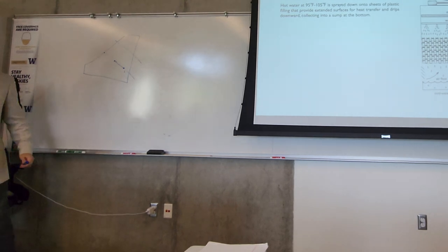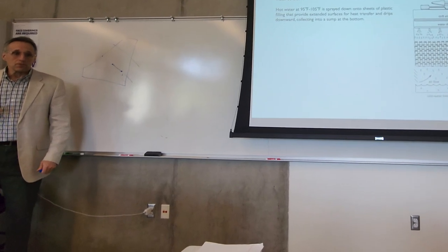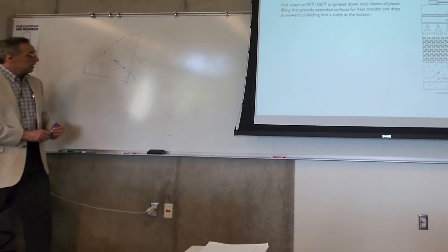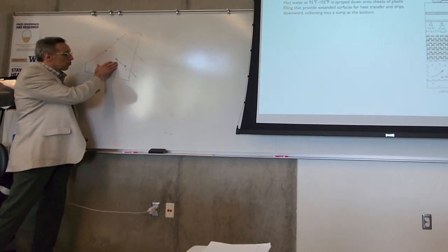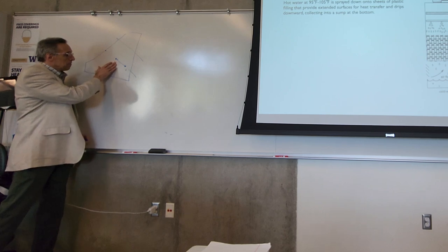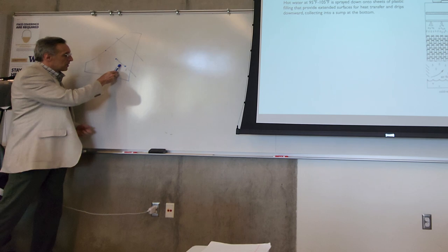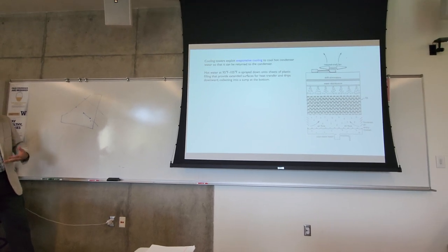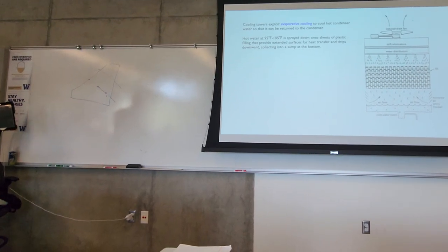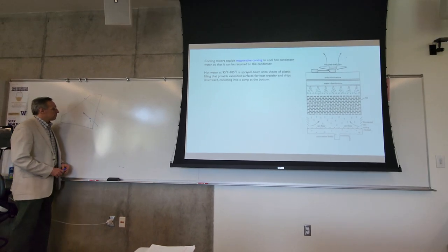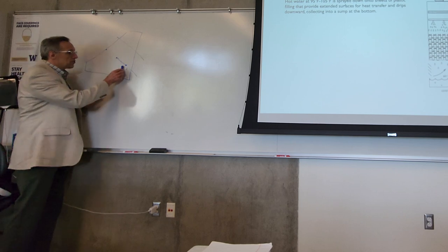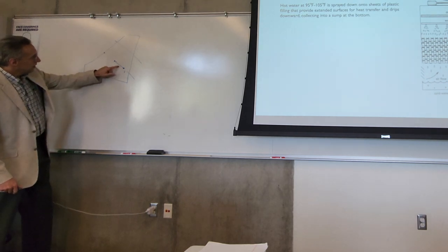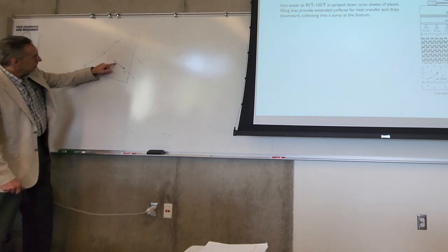And there are actually, you know, some humidifiers work that way. Some humidifiers spray steam if it's in the wintertime. In the summertime, you might spray cold water. But typically, and with cooling towers, you're working with the water as it's coming to you. Well, actually, in a cooling tower, the water is typically warmer than the air. So on a really, really hot day, it can be cooler than the air. But this is generally what's happening. You're roughly in a cooling tower, constant enthalpy cooling of the air.